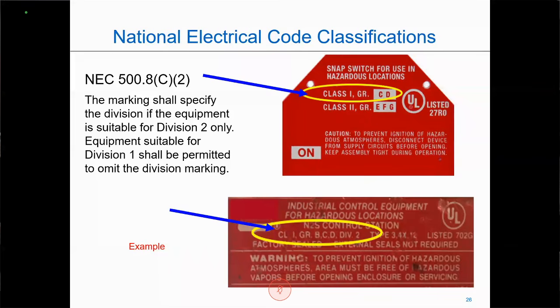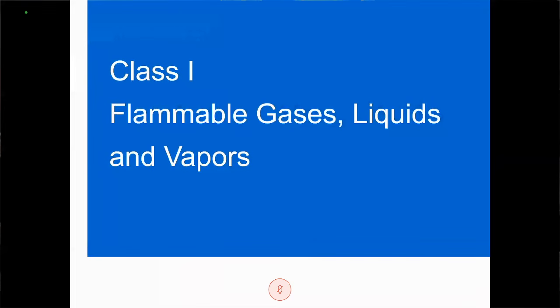Now, this is a little bit rarer as time goes on because a lot of manufacturers have begun to understand that while the code doesn't require you to write Class 1, Division 1, it does create some confusion. So this is something that you're not seeing as often as you used to. Now we're going to take a closer look at the area with the flammable gases, liquids, and vapors, our Class 1 area.